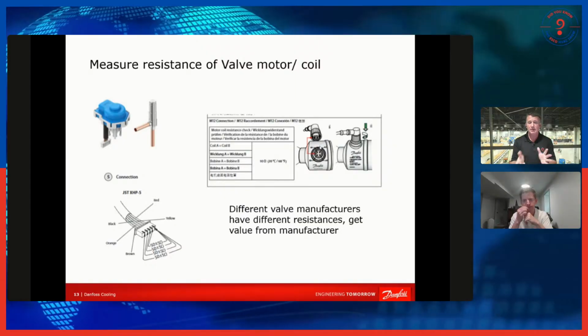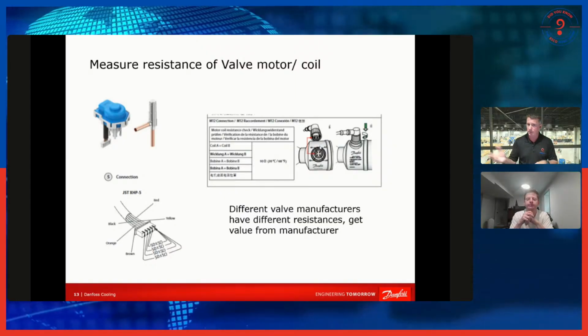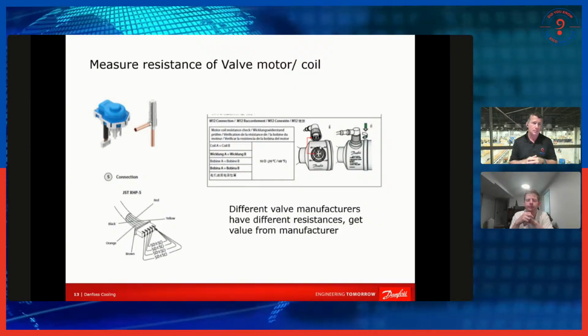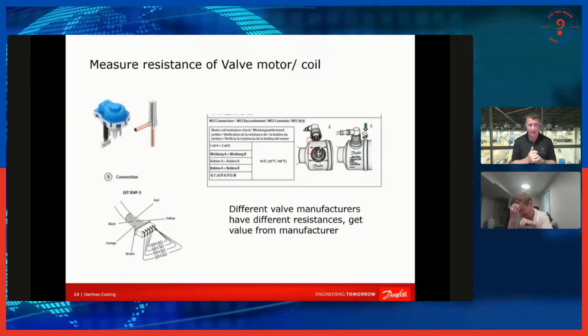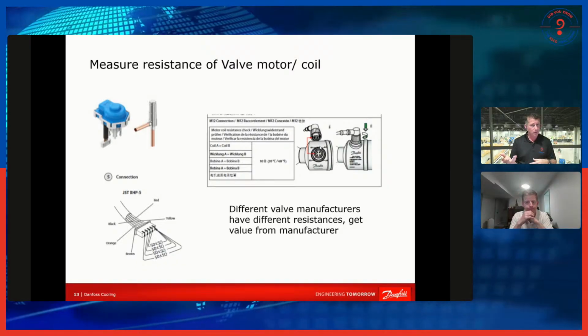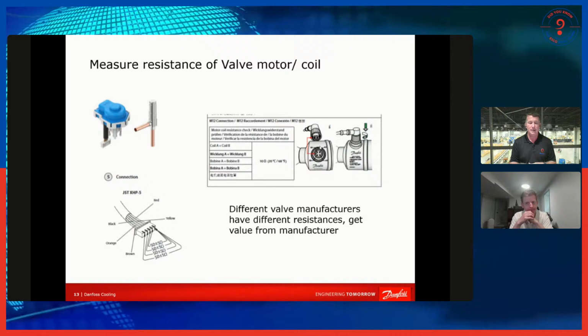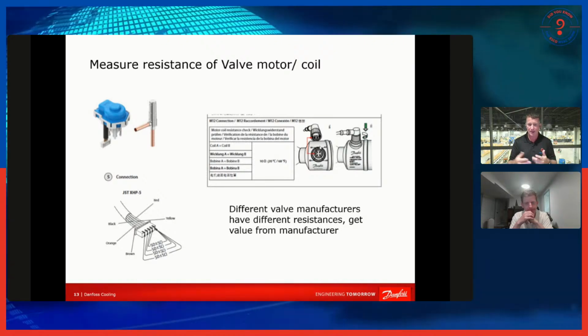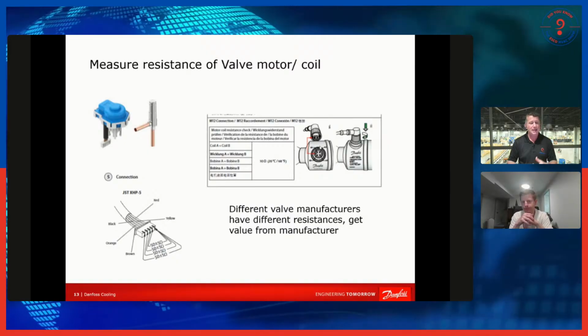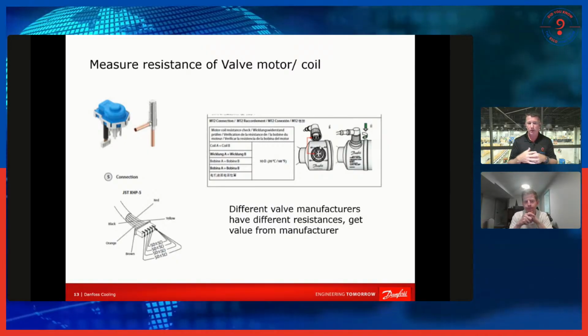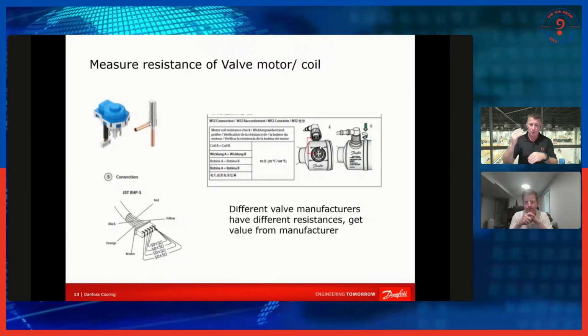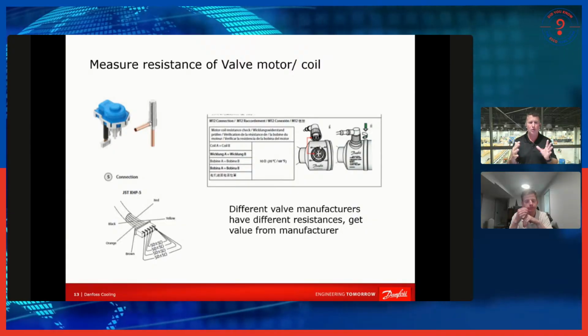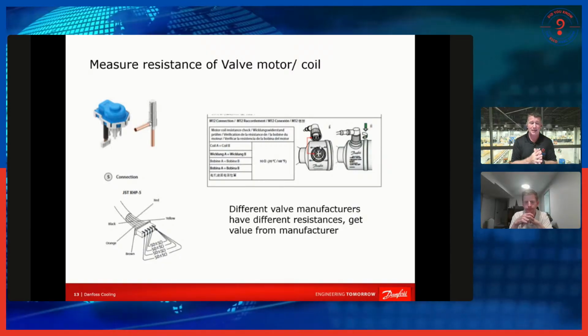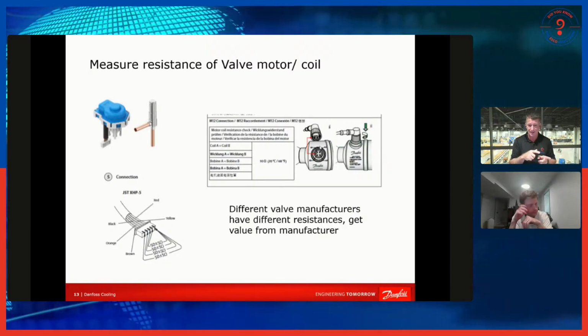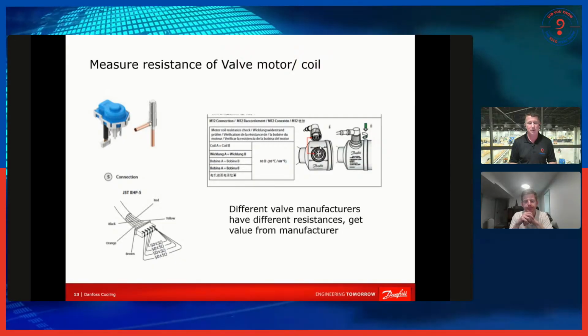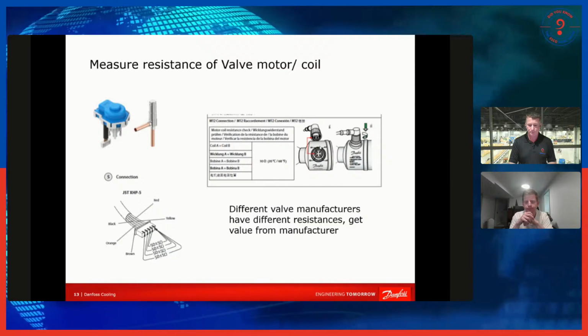And that was one of the scenarios that I encountered on a new piece of equipment. It was quite a few years ago, but it was a newly installed system that was only getting partial capacity. And what we found was that it was calling for full capacity, but we had one of those windings that was open, and so we could only get a partial capacity out of the system. And you're right, it would shut down completely. And so my opinion was that, depending on what phase it is, we could get some partial opening or closing, but not 100% control of that electronic expansion valve. And we may not get an error code unless the controller was designed to read resistance through the connections, but it's not a common practice that I've seen. Yeah.